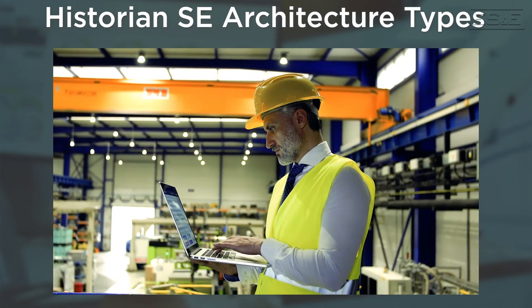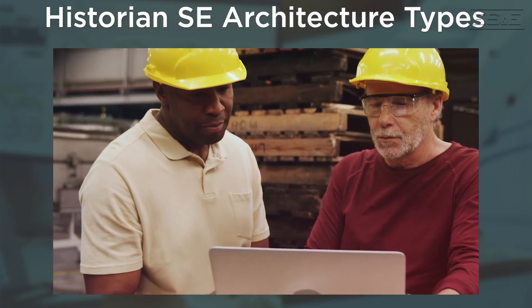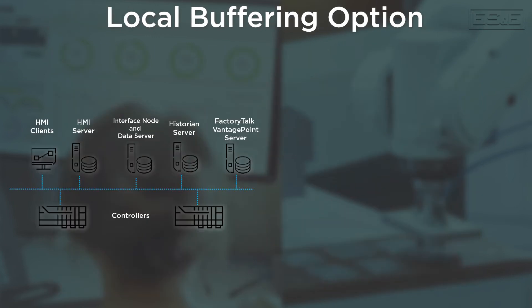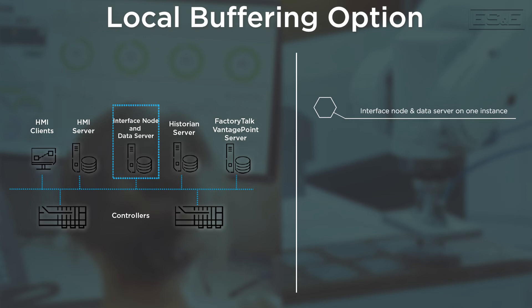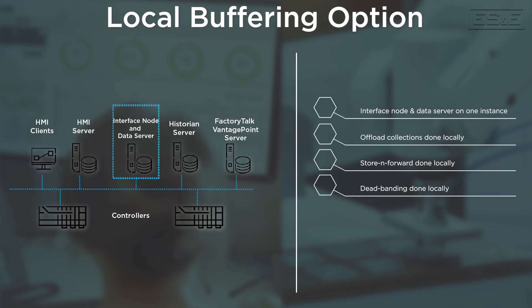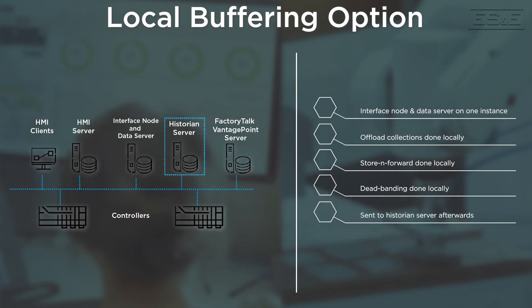Let's talk about some of the typical architectures you will see when implementing Historian SE. One of the simplest is what we call the local buffering option — that is when you have the interface node and the data server all located on one instance or one OS. Data collection, store-and-forward, and dead-banding are done at that local machine and then sent to the Historian SE server. The only split is the interface node and data server on one machine, and the historian — which does the archiving and asset framework — on a different machine.